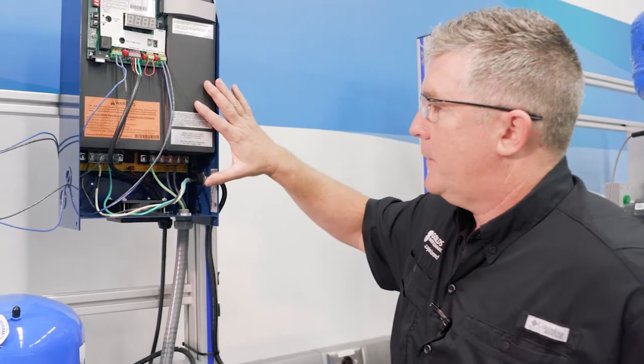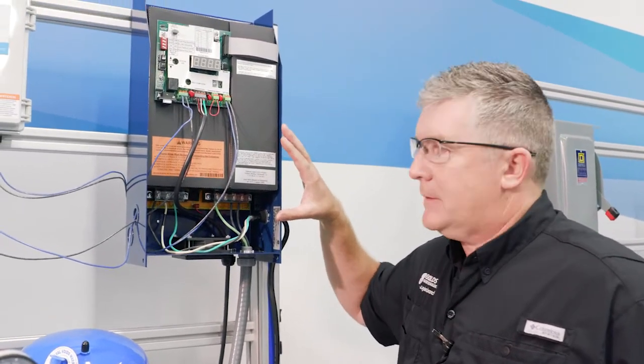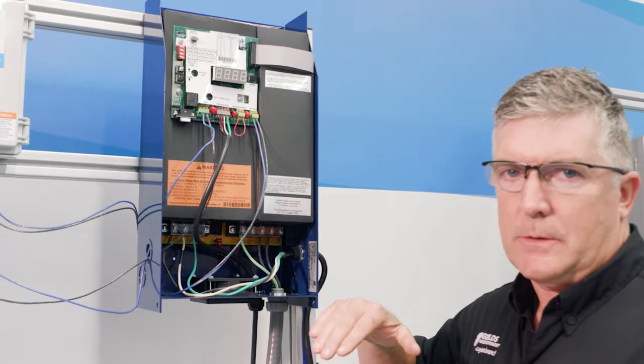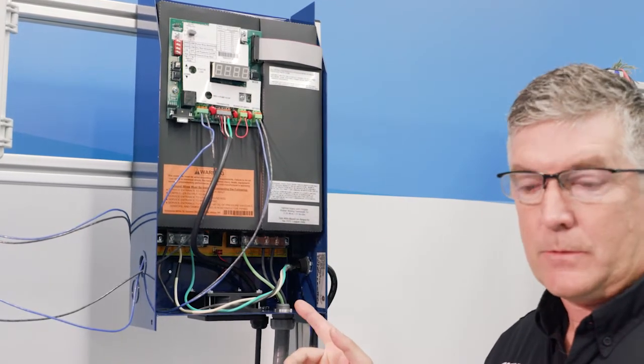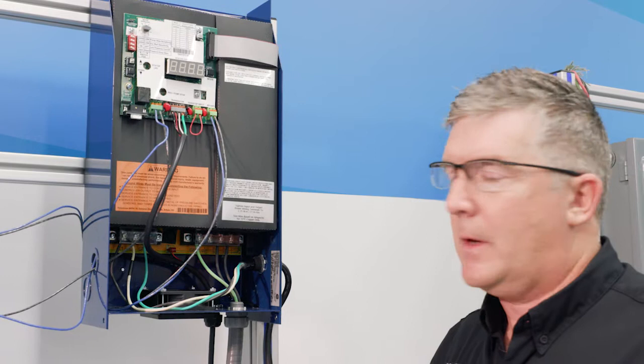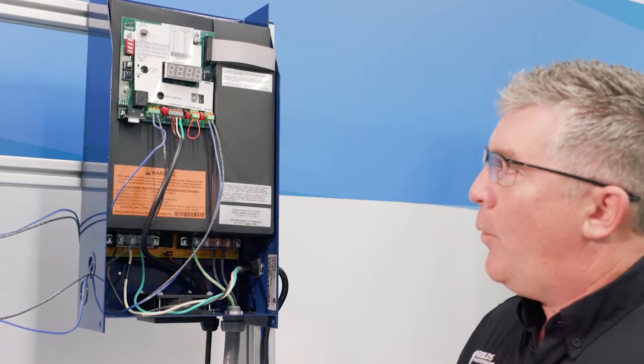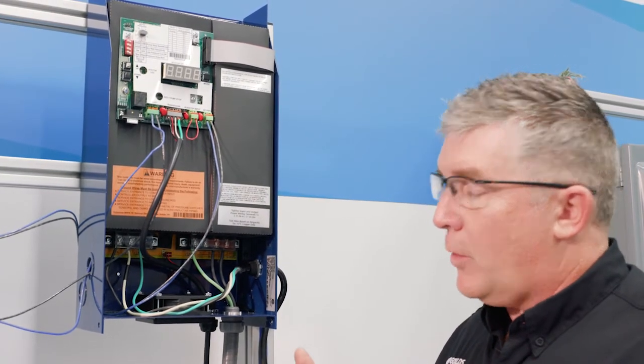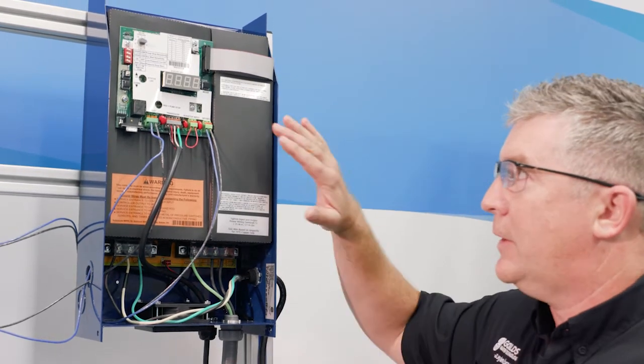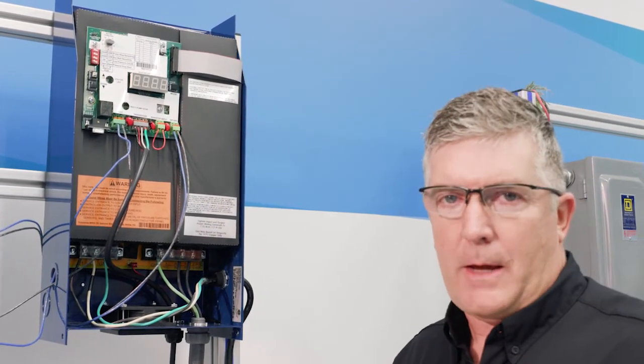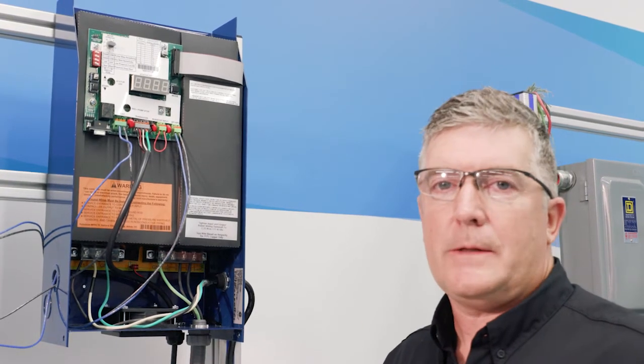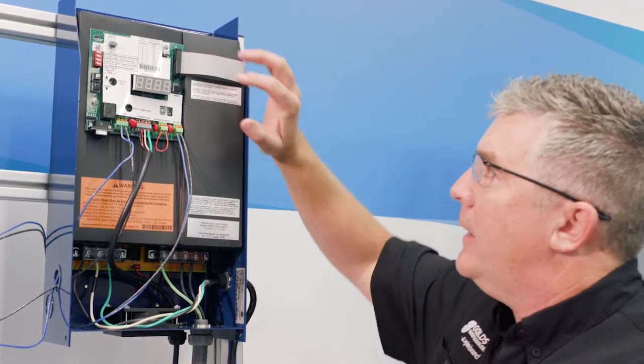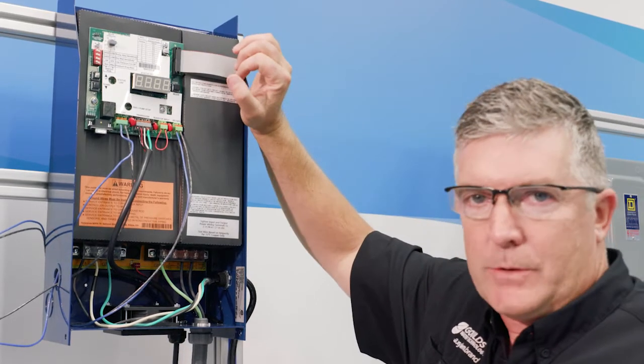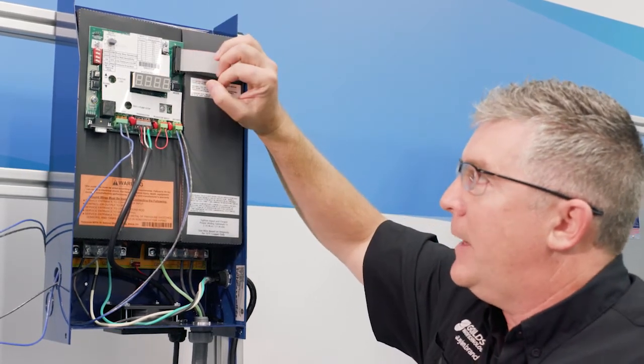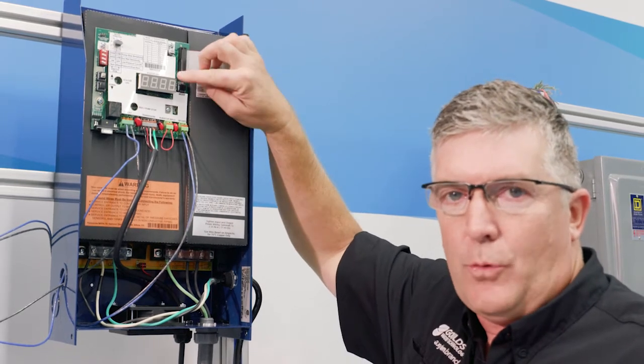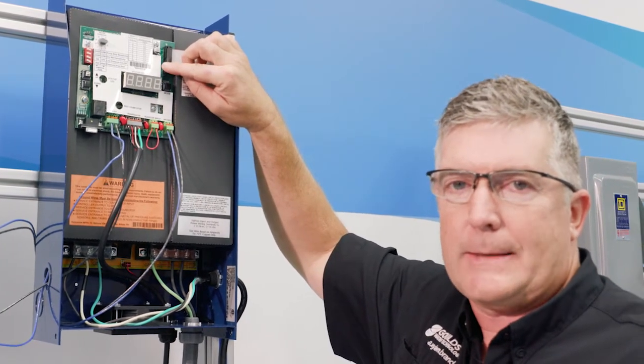So if we look at the 1AS15, the 1AS15 is single phase input, single phase output. So we're using just a standard single phase motor. And the 15 is horsepower, and it basically says we're good to roughly a horse and a half. At the end of the day, it's really about amperage. And if we look up here to the max amperage, it tells us we can handle a pump that goes up to 12.2, and that would be service factor max amps.